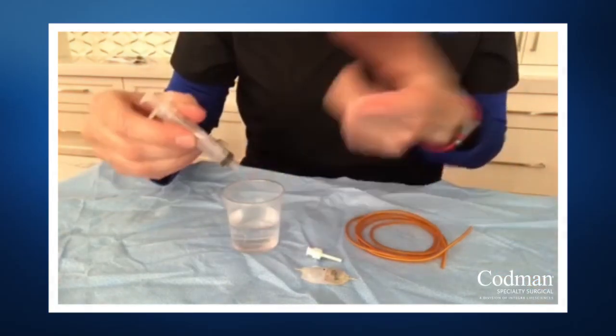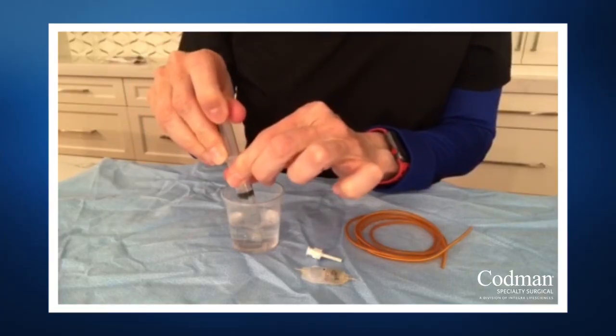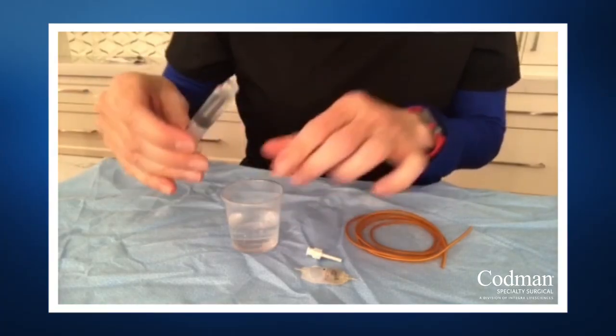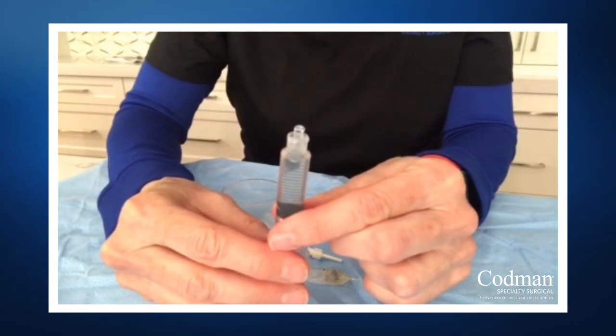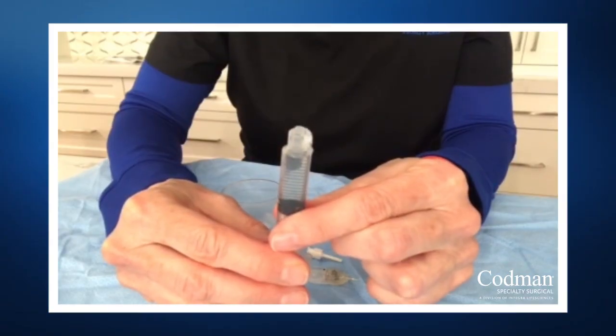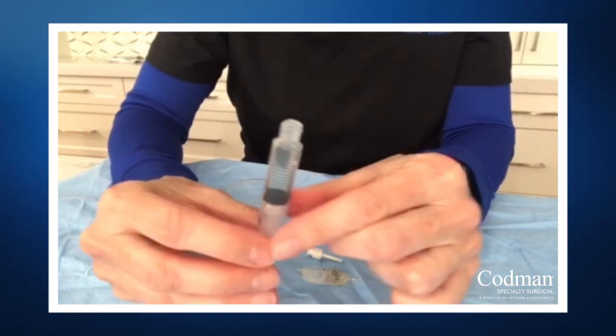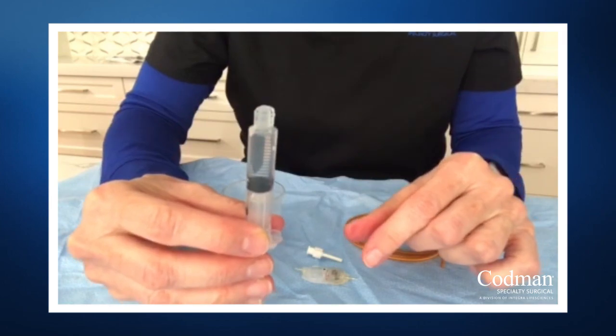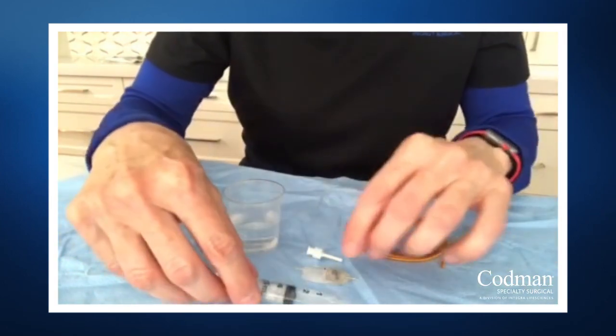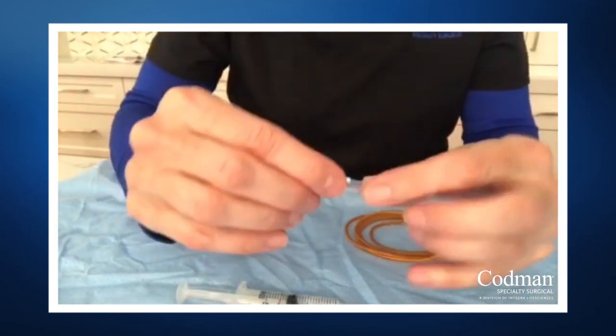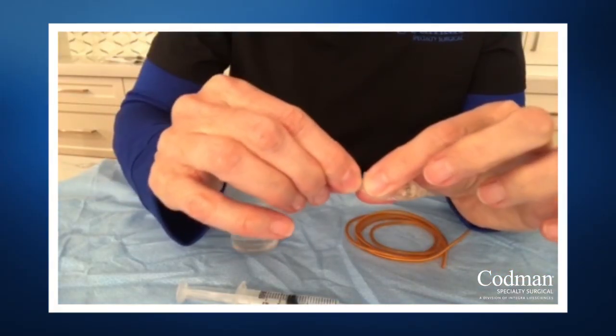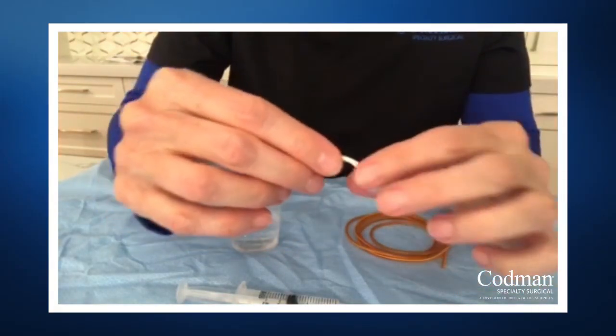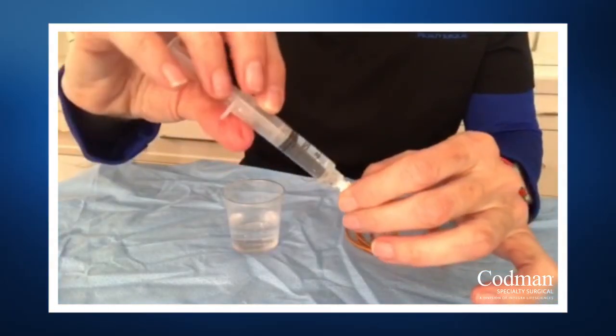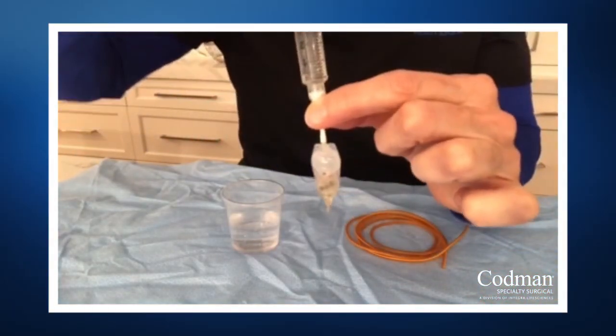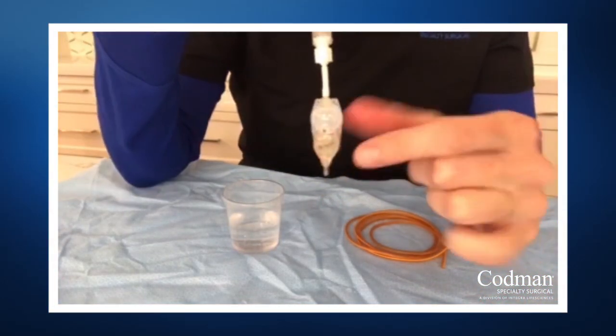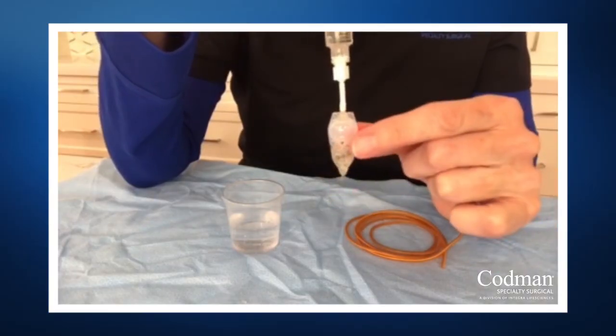Basically, you're going to take your syringe and you're going to fill it with your solution. And it's important to push out any extra air bubbles that may be in the syringe, because one of the goals in priming the valve is to minimize air bubbles and to push all the air bubbles out. Then you'll take your priming adapter and hook that onto your CERTAS valve as such. And then you're going to hook your fluid-filled syringe to the valve, and you're going to point the valve with the outlet portion pointing down towards the floor.